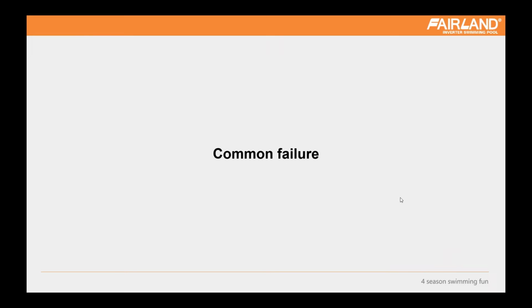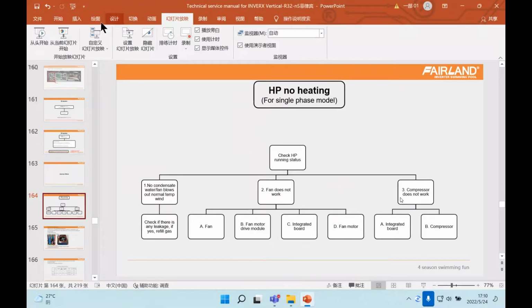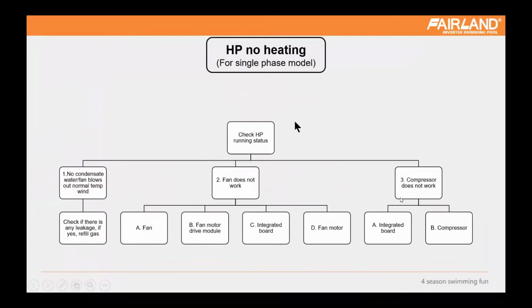And the next part is for common failures with no codes, like the heat pump not heating. Once the heat pump is not heating, we will check three parts. You will go to the unit and see if the unit has condensed water, and feel what the fan blows out, if it is cold, the unit is heating. You will see if the fan is running or not, and the compressor is running or not. Where there is a problem, we will fix it.